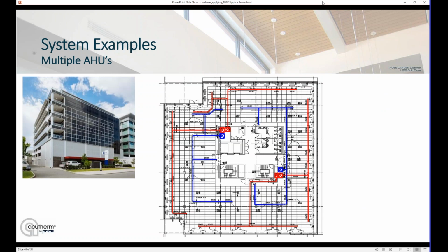I mentioned earlier, this is not an approach limited to small buildings. This is a multi-story little office building you can see there, and they've used 6 different air handlers in this case to zone the building, 1 for each face of the building. Again, to avoid the need for reheat. And in this particular instance, they split the interior into 2. Again, a very effective and energy efficient approach. Because this is a multi-story building, though, it's not an all low pressure approach. There'd be a modulating zone damper on the takeoff to each floor. The ductwork on each floor then being a low pressure zone, medium pressure up and down the risers, and fan speed control to maintain that medium pressure section.